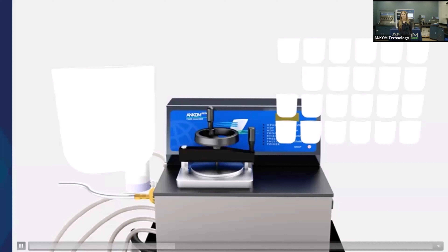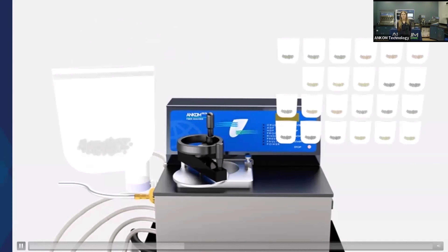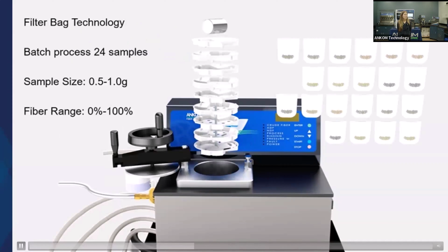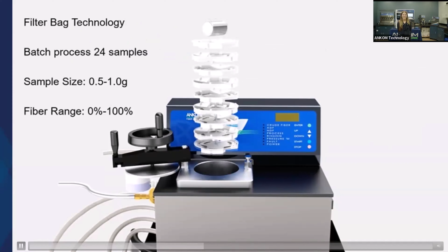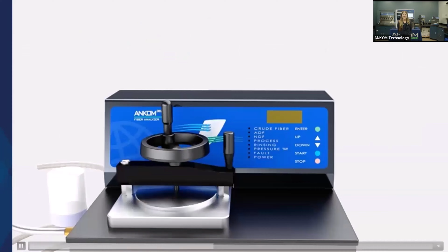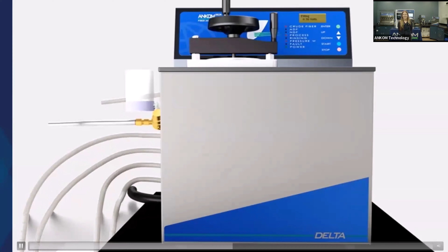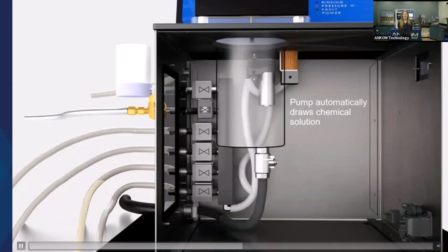Up to 24 samples are prepared and encapsulated in filter bags. The filter bags with sample are sealed, placed in a bag suspender, and placed into the fiber analyzer's vessel. After the user closes the vessel lid, they follow simple screen prompts to select the desired method and start the run. The Delta's internal pump system automatically draws the appropriate chemicals in the program sequence per the selected method. One of the 5 solution valves opens to allow the pump to draw the chemical required. A fiber optic sensor indicates when the correct volume of solution has been delivered and the vessel is full.